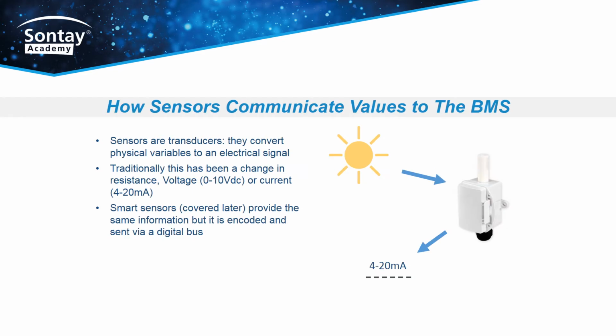How sensors communicate values to the BMS. Sensors are transducers. They convert physical variables to an electrical signal. Traditionally, this has been a change in resistance, voltage 0 to 10 volts, or current 4 to 20 milliamp. Smart sensors, covered later, provide the same information, but it is encoded and sent via a digital bus.